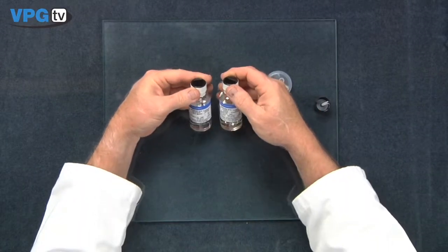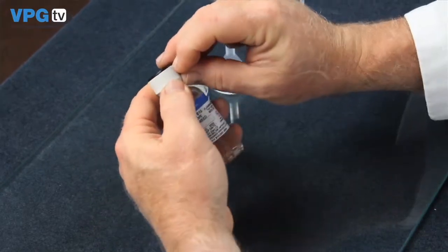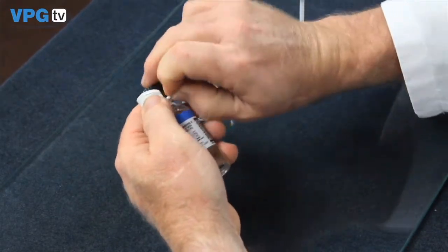Step one will be the proper mixing of the adhesive system. Before mixing, be sure to check the expiration date on the M-Bond 610 adhesive and curing agent bottles. Out of date materials should not be used.